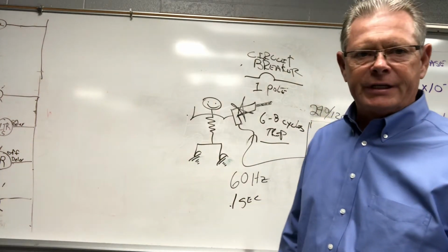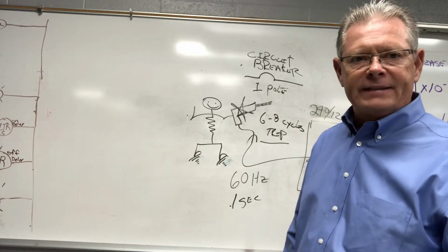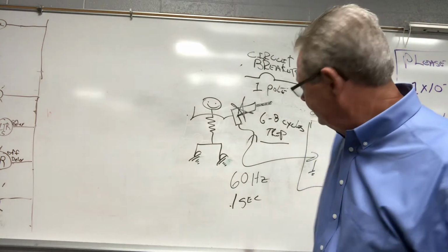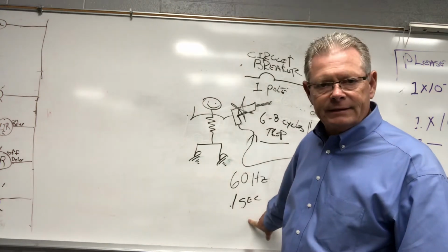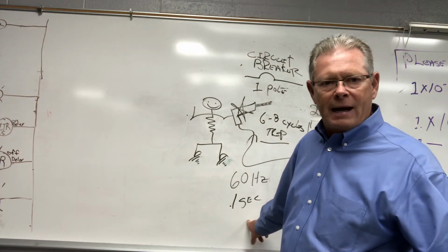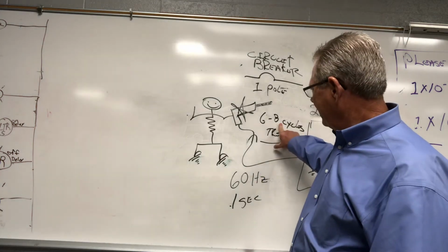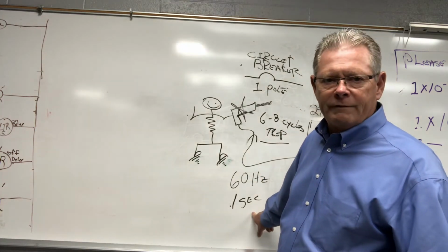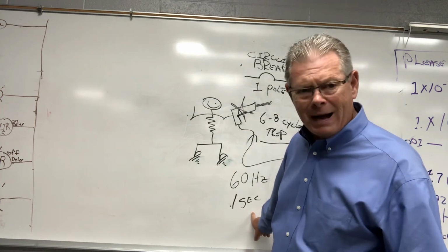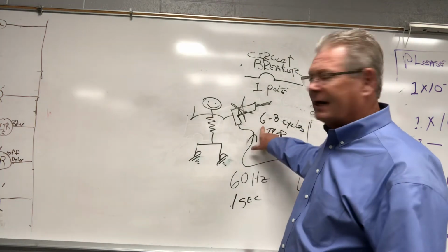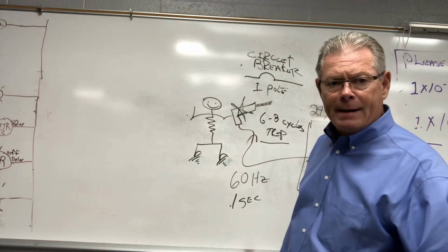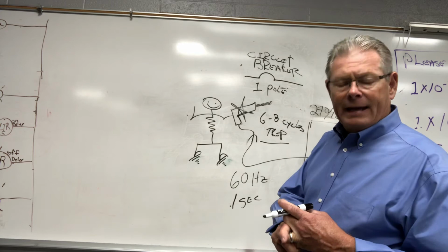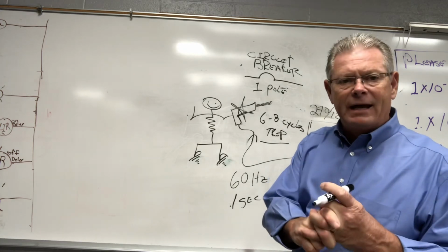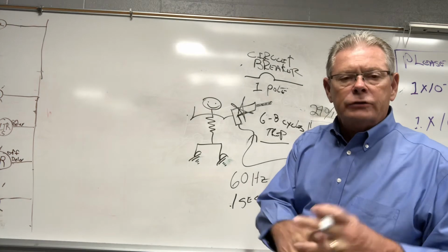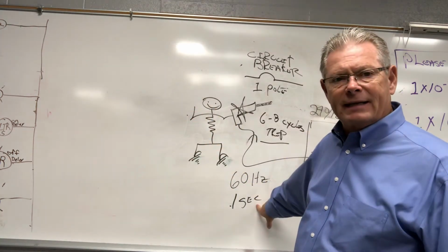Now, how fast does electricity go? What's the speed? It's the speed of light, right? 186,000 miles per second, or 300 million meters. So in 1/10 of a second, electricity travels over 18,000 miles. So 6 to 8 cycles, it'd be between 0.1 and 0.15 seconds. So we're talking over 20,000 miles electricity goes in the time it takes that breaker to trip, because it's an inverse time breaker, it trips on heat. And it has to, the physics of it, heat up before it can trip and open the circuit. So during that 6 to 8 cycles, that 1/10 of a second, yes, the answer is yes.